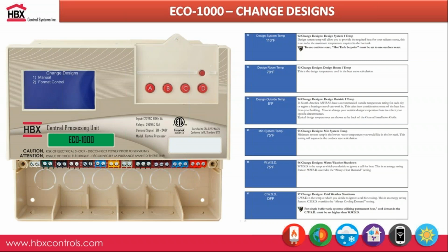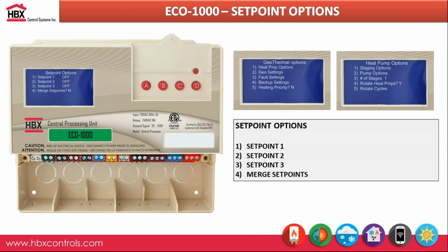That's how we do the automatic switch over in terms of the Eco 1000, as well as the heating and cooling demands that the controller receives. So you never have to manually adjust it from heating to cooling. It'll just do that off the demand outputs, as well as the functionality of the cold weather and warm weather shutdown.